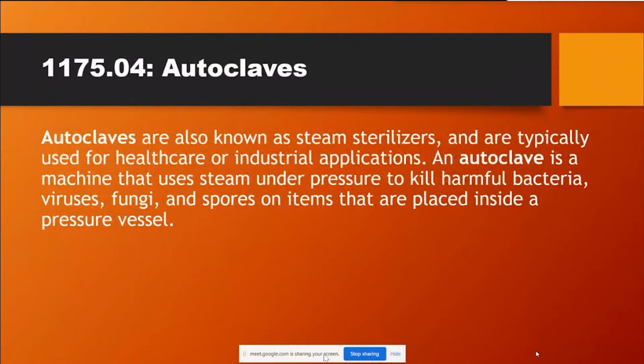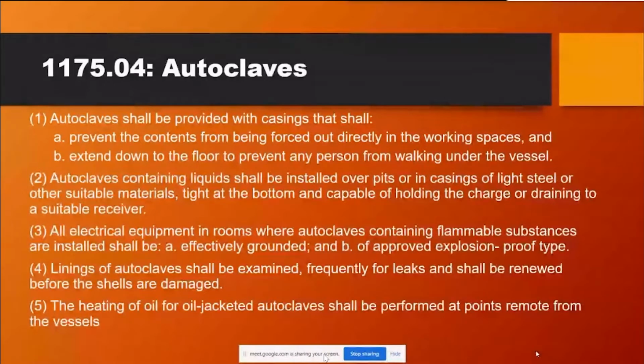Autoclaves. Autoclaves are also known as steam sterilizers and are typically used for healthcare or industrial applications. An autoclave is a machine that uses steam under pressure to kill harmful bacteria, viruses, fungi, and spores on items that are placed inside of pressure vessels. Autoclaves shall be provided with casings that shall prevent the contents from being forced out directly in the working spaces and extend down to the floor to prevent any person from walking under the vessel.